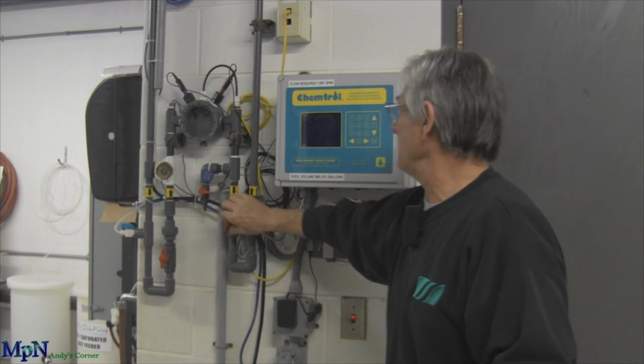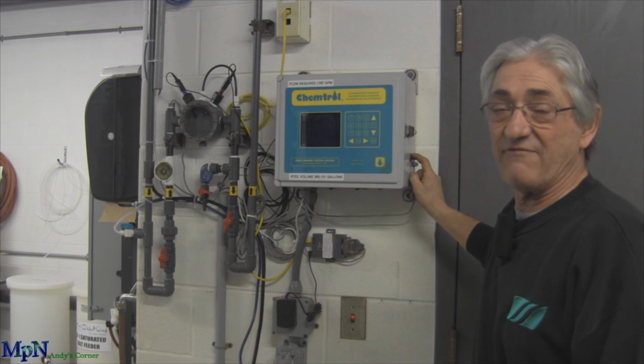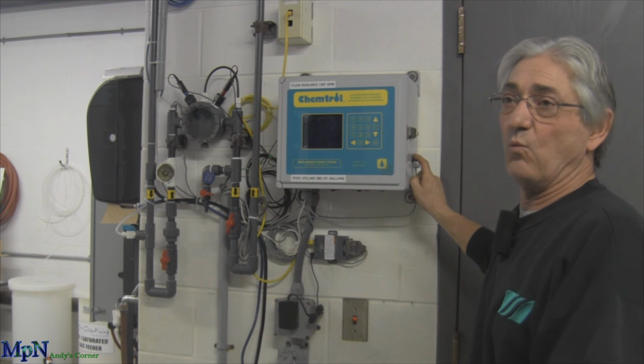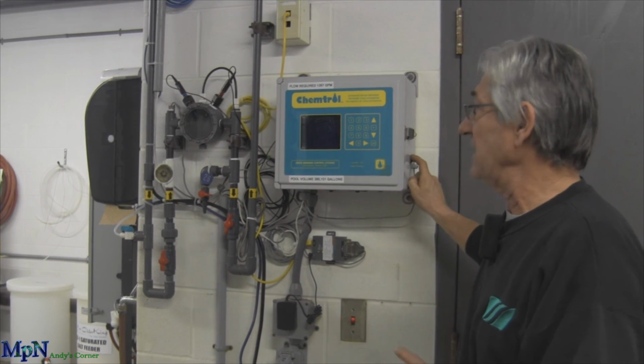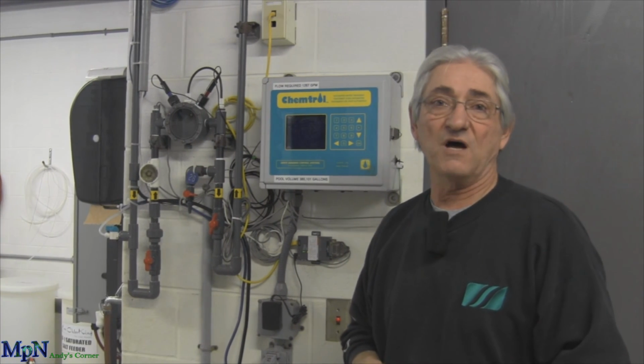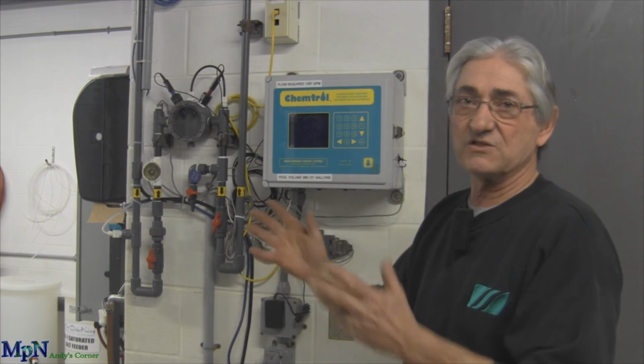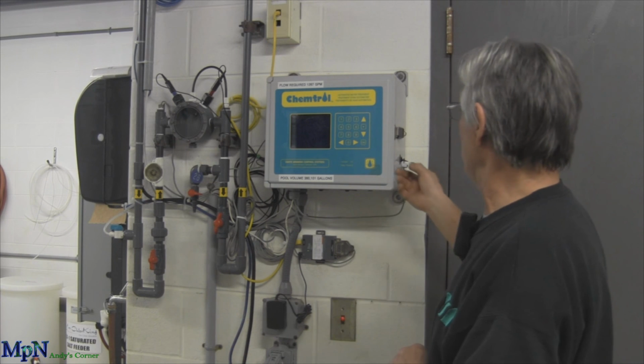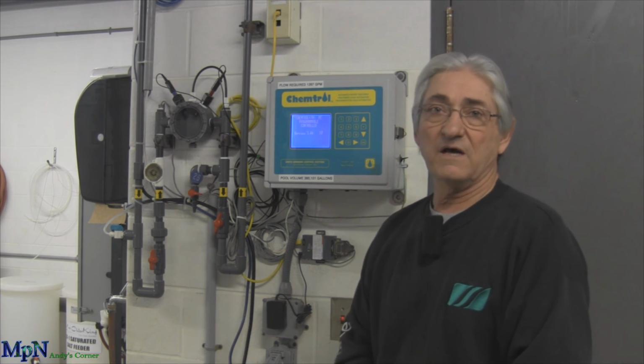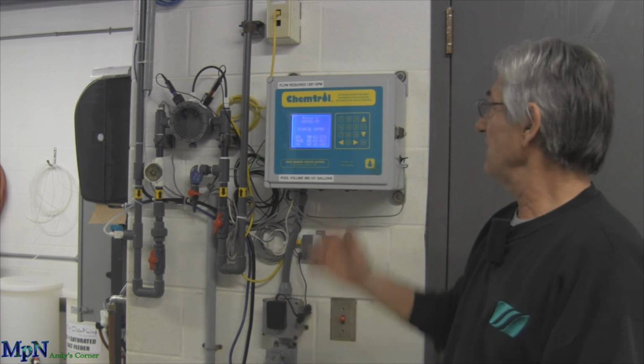While you've got the flow on, you want to make sure that the switch is off for about a half hour to an hour, because whatever you use to clean the probes is still on that probe until it gets washed off. Half hour or so, once it's settled down and it's not moving all over the place, you can turn the controller back on and make sure you're back in automatic.